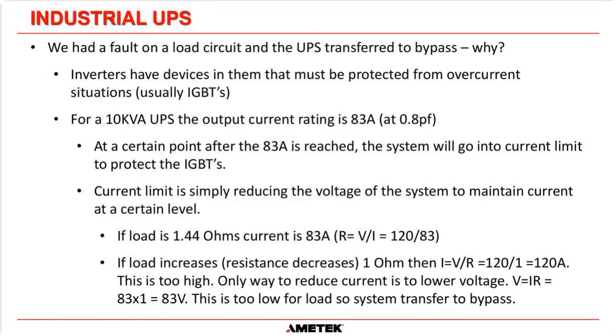So for a 10 kVA UPS, we've already mentioned before on a single phase system, the output current rating is 83 amps. So at a certain point, let's say you have a fault somewhere on your load circuit. If that fault current goes above 83 amps, the system will go into current limit to protect the IGBTs, okay? Because the system designer, in truth, we use oversized IGBTs, so you are going to have some protection, but let's say the designer put 100 amp IGBTs in there. What we're saying is if the load fault asks for more than 83 amps and it goes above 100 amps, those IGBTs could fail catastrophically because you can't protect an IGBT with a fuse.